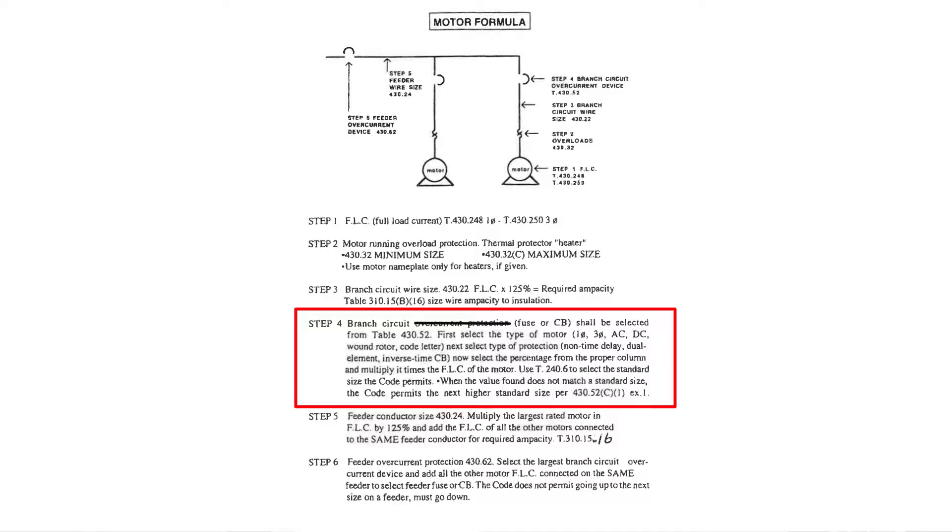Then it says next select the type of protection, whether it's a non-time delay fuse, a dual element time delay fuse, the inverse time circuit breaker, or not listed here as an instantaneous trip circuit breaker - four different things. It says now select the percentage from the proper column and multiply it times the full load current of the motor. Then it says use table 240.6, guess what you got glued in right there, table 240.6, to select the standard size the code permits.